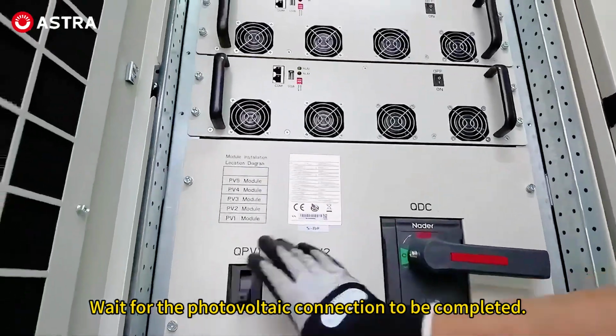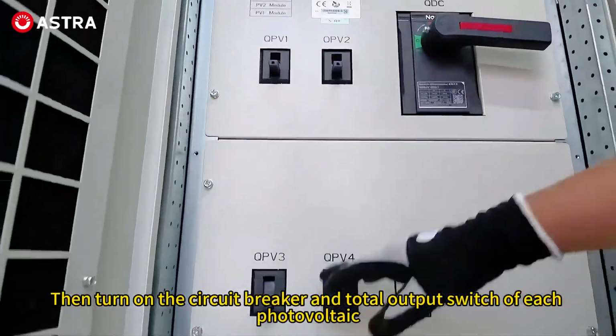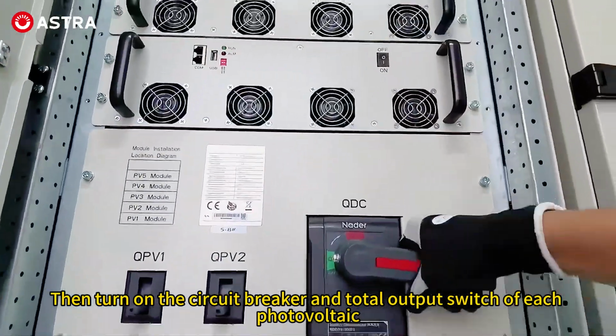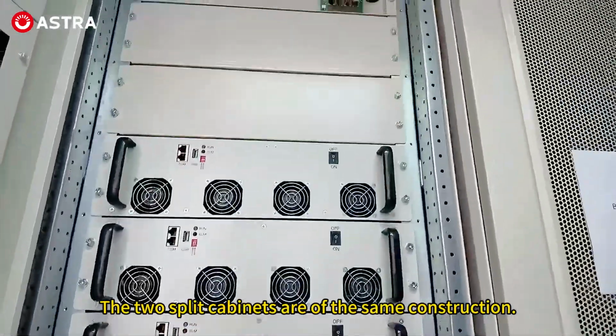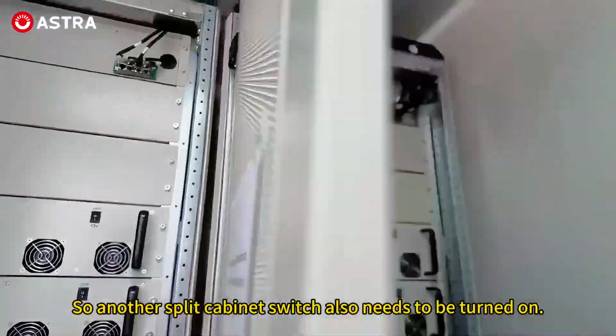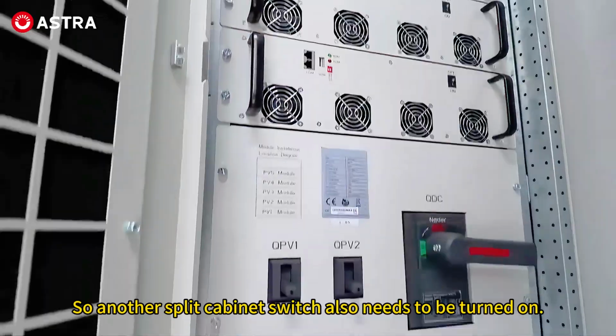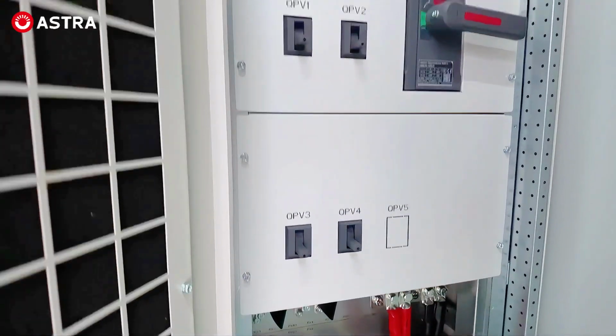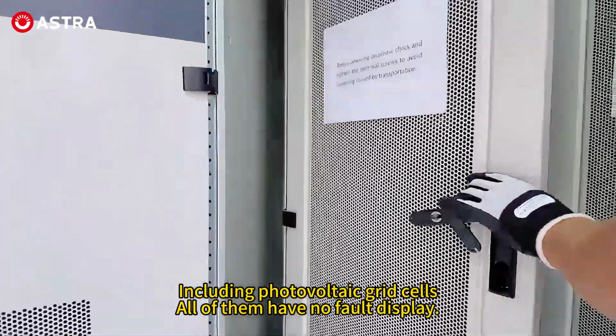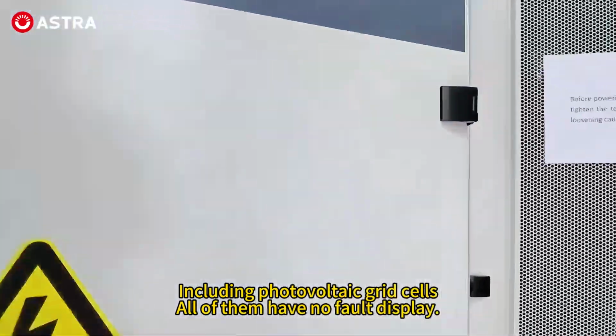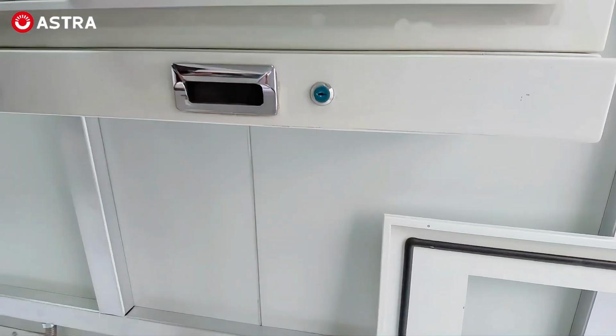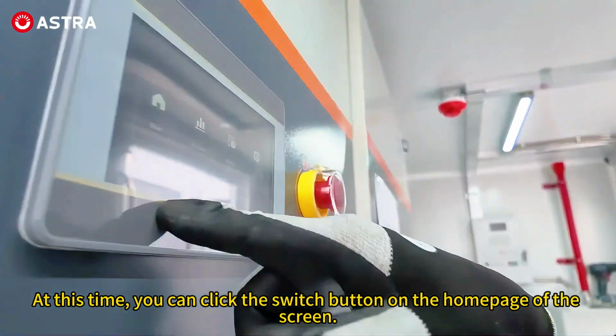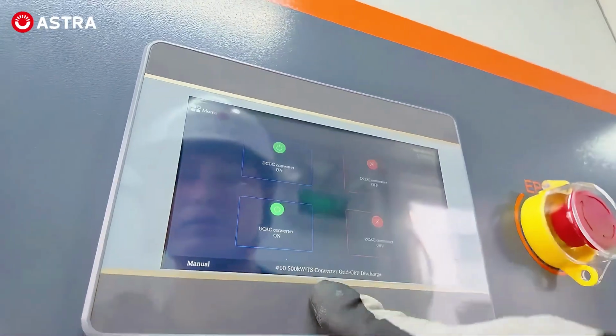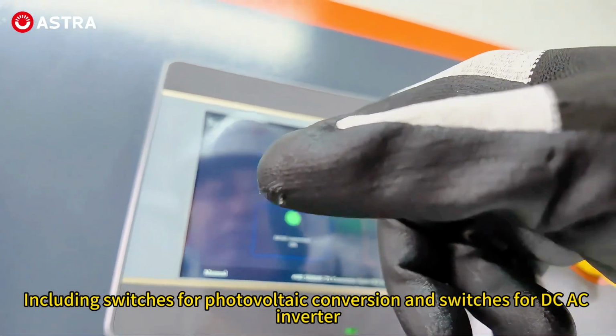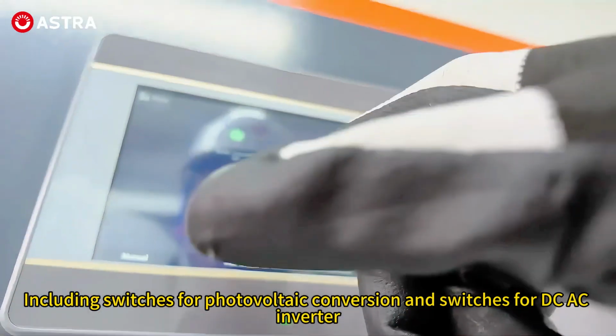Wait for the photovoltaic connection to be completed. Then turn on the circuit breaker and total output switch of each photovoltaic. The two split cabinets are of the same construction, so another split cabinet switch also needs to be turned on. When everything is ready, including photovoltaic and grid, all of them have no fault display. At this time, you can click the switch button on the home page of the screen, including switches for photovoltaic conversion and switches for DC-AC inverter.